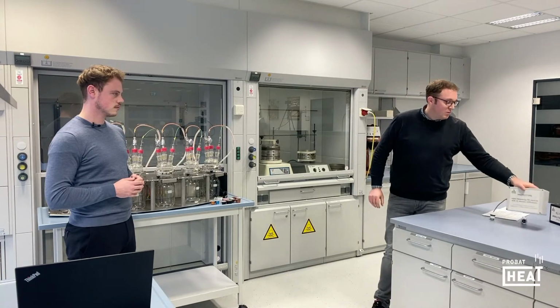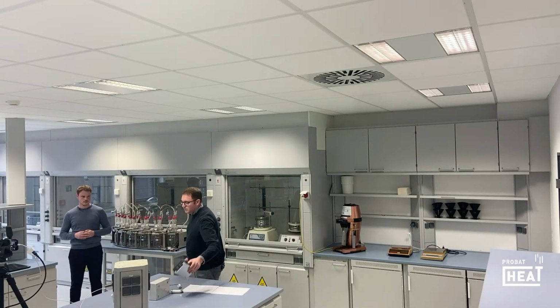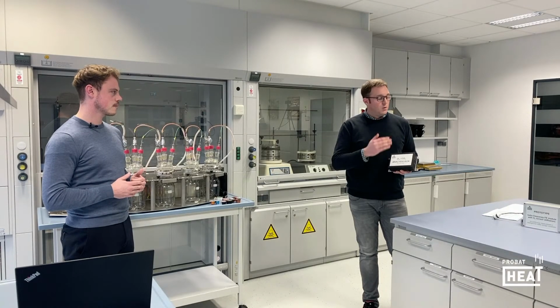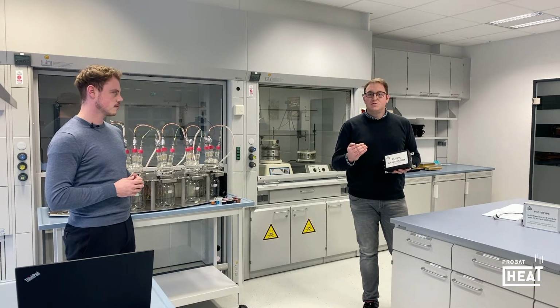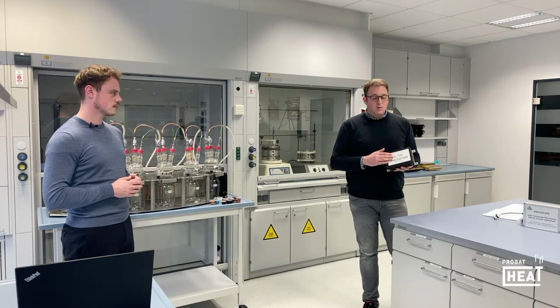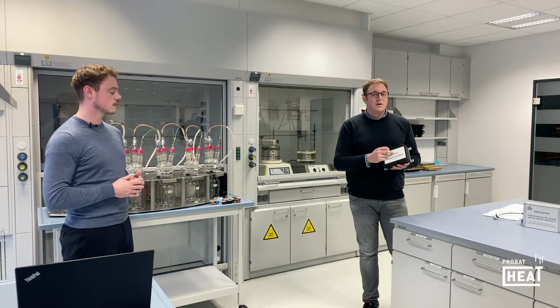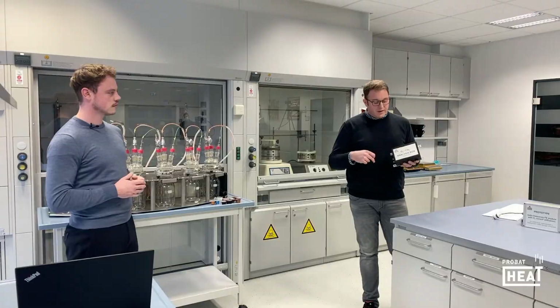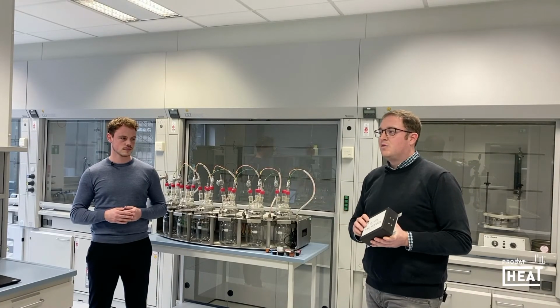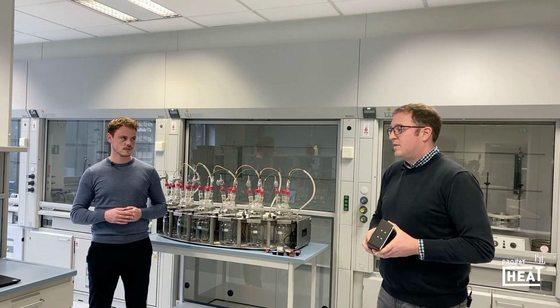And we talk about the oxygen transmitter box. Inside this box we have a forced flow, whereas with the other one we have diffusion. So the gas must go to the sensor. Here we have a small pump inside. We have a pre-filter, then a small pump, and then the oxygen measurement system. The gas comes in, and on the other side the gas goes out, maybe back to the silo or whatever.